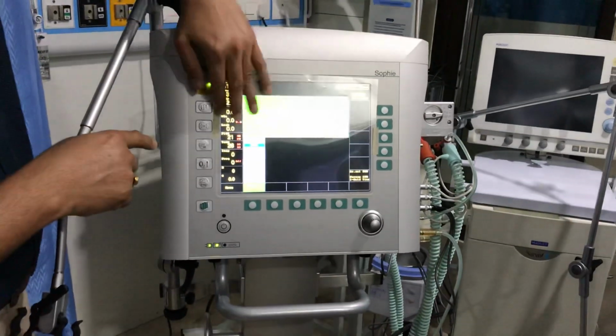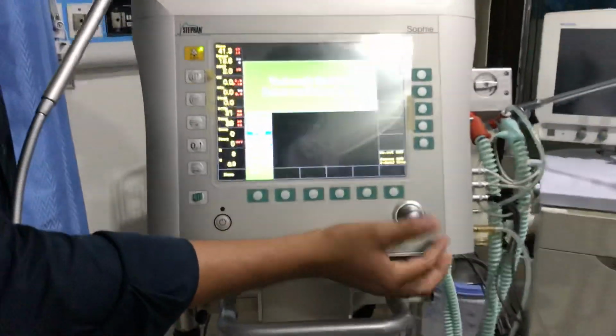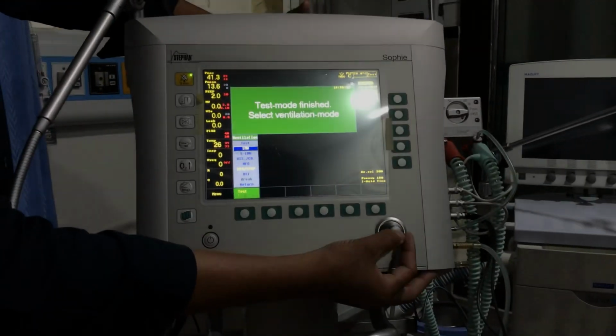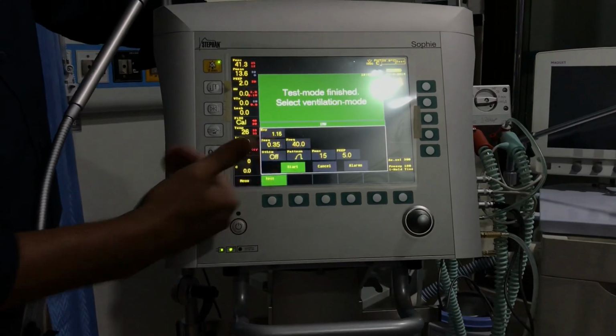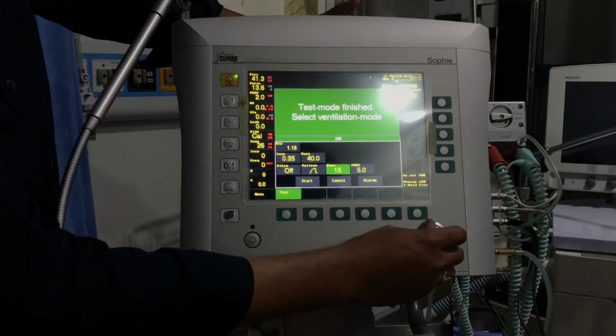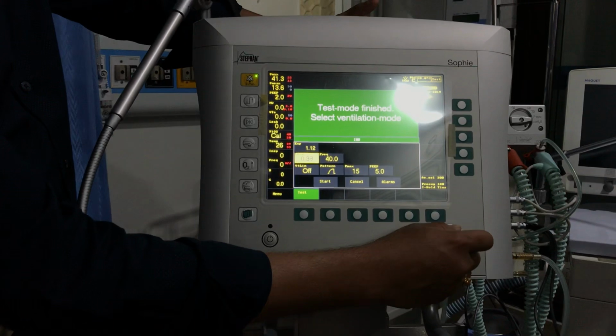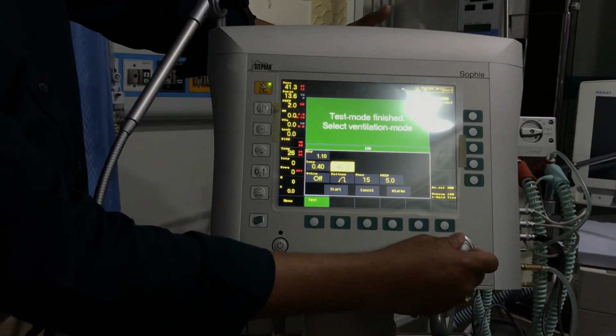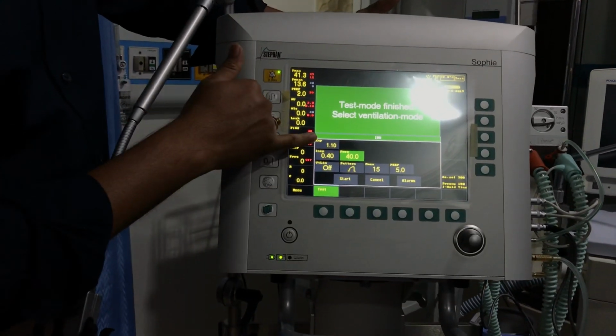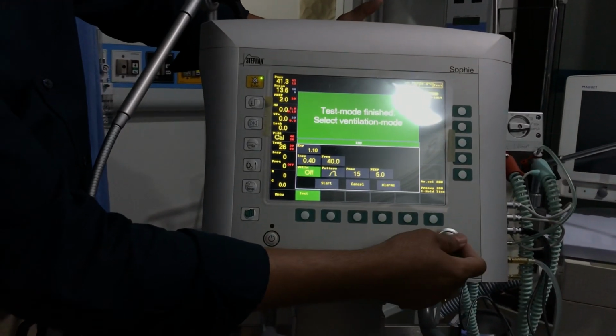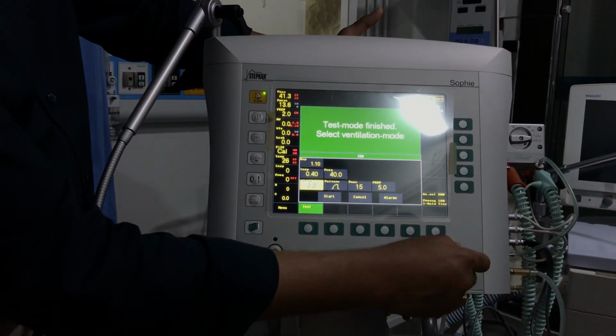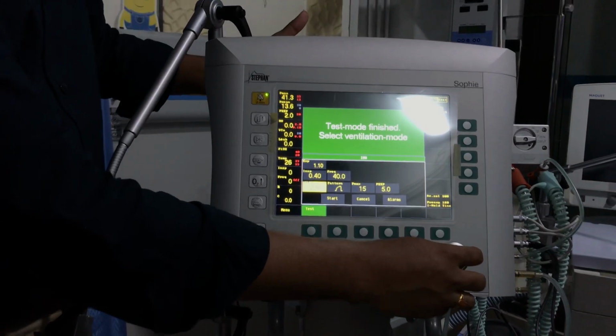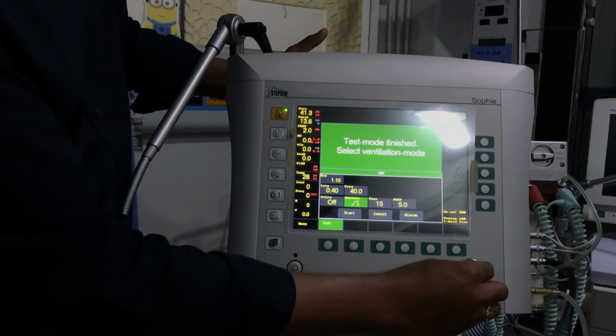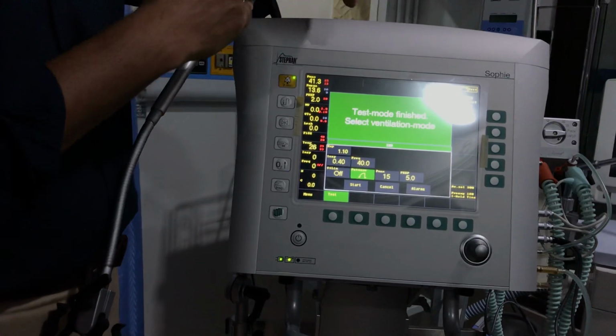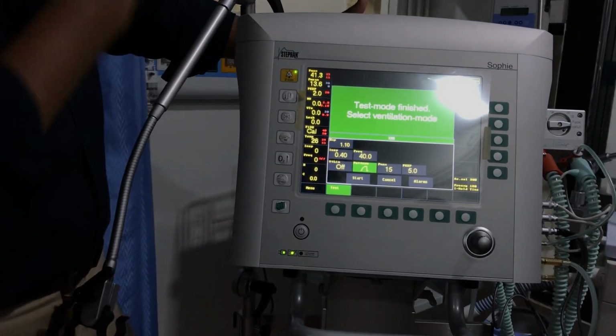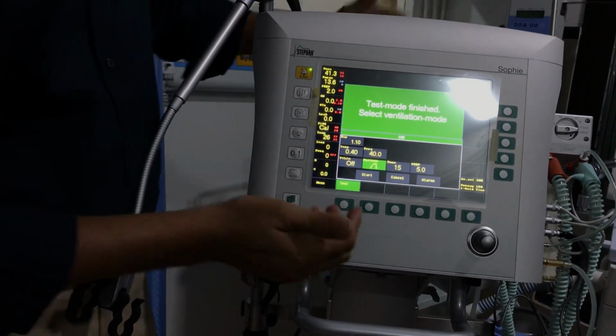So you can see test mode finished, ventilation mode. Now this is the single knob operation. I can select any mode like IMV, and then the required parameters will be displayed. We have the inspiration time in seconds, we can set that, and the frequency, respiratory rate. Automatically your expiratory time gets set. Then other parameters like volume limit or volume target ventilation, I can set. You can go up to 150 ml. Then flow pattern, that is basically acceleration from peak to PIP. Instead of rise time, we have given the flow patterns.